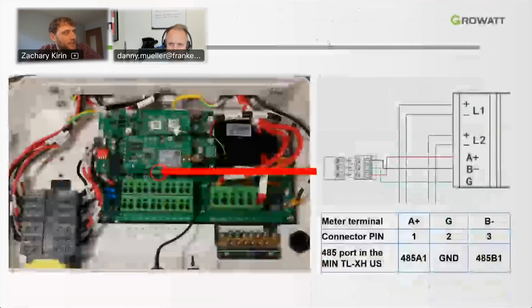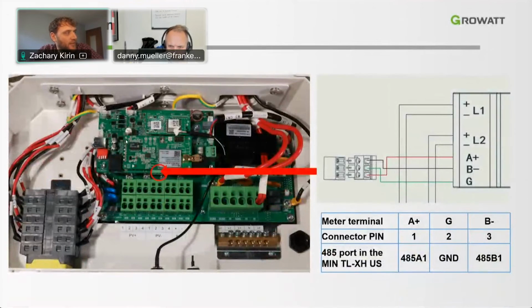So the smart meter installation will be here. This is where the smart meter Modbus, the A plus and the B minus, so this is the TX and RX, receive and transmit, will be input to the inverter. We're just going to make sure that we have the proper connector pins connected in the proper fashion. So A plus would be on 1, ground would be in the middle, so 2, and then B minus is the very end, 3.